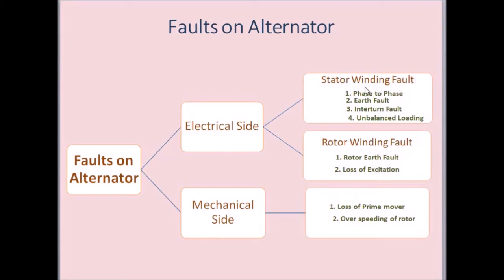Therefore, there is a possibility of phase-to-phase insulation failure, causing a phase-to-phase fault inside the alternator. There is also a possibility of insulation failure between any one phase and the core of the alternator, leading to an earth fault in the stator winding. There may be insulation failure between any two adjacent turns on a phase winding, and there may also be a possibility of unbalanced loading on the terminals of the alternator.